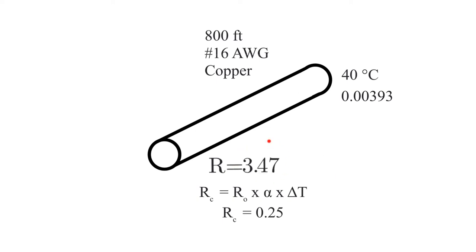In this case, that's going to be 3.47 ohms. So again, you take your original resistance, multiply it by the coefficient of temperature for the material you're using, whether that be copper, aluminum, silver, any of those.